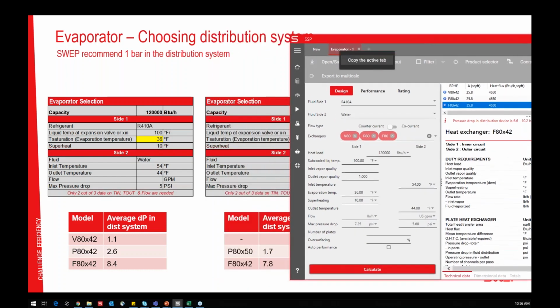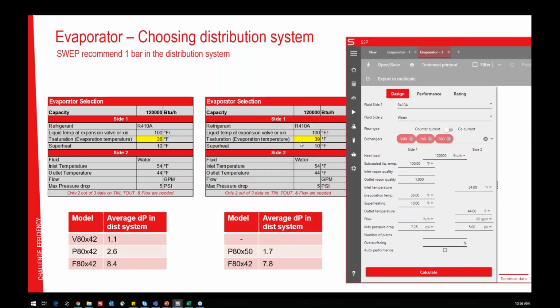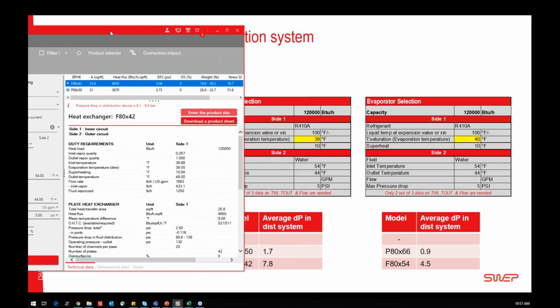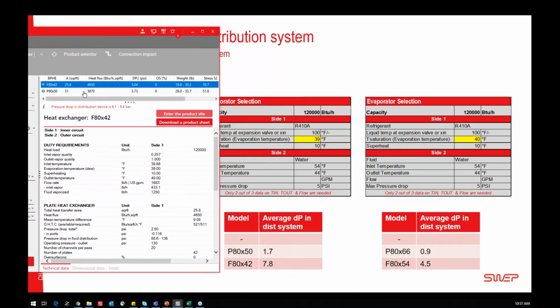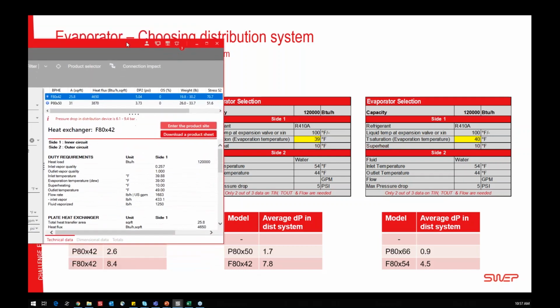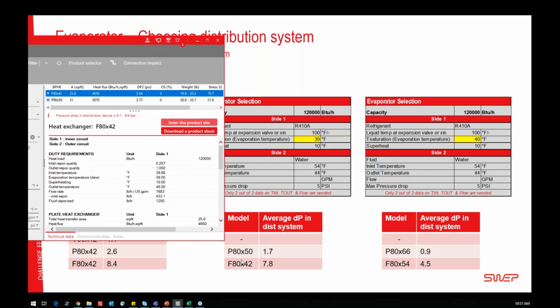So we do the second one, which is exactly the same data. The only difference is that now the target evaporation temperature is 39. We run again. And what do we get? Well, the V80 is out of the question. It's not even selected anymore. The F80 is still with the same number of plates as before, but now since the evaporation temperature is higher, the pressure in the distribution system has gone down from 8.4 to 7.8. And the P80 is still in the game, but had to increase the plates a little bit. Not so much, but a little bit. And here we have now a pressure drop of 1.7. So there seems to be something with the distribution system, doesn't it?